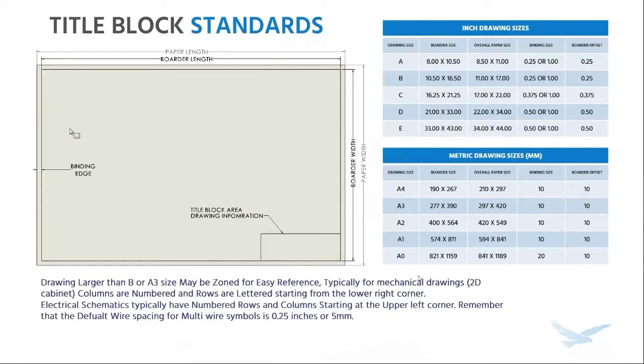Things to keep in mind: larger title blocks in the mechanical world have typically been zoned with alphanumerical characters for columns and rows. Electrical also uses columns and rows, but ours are typically numbered. When establishing rows and columns in your drawings, keep in mind the default wire spacing for symbols in electrical, which is a quarter inch or five millimeters.